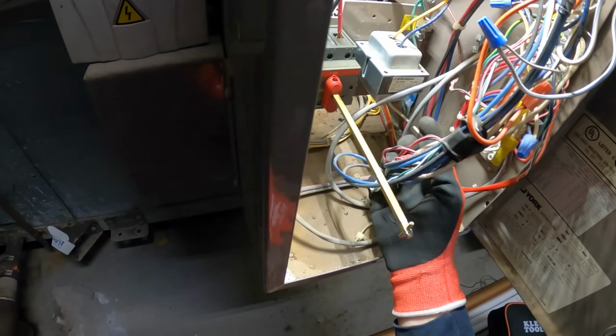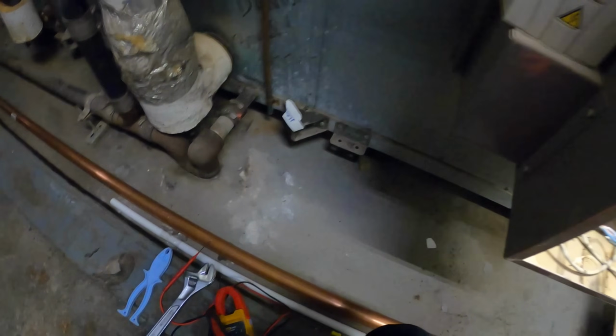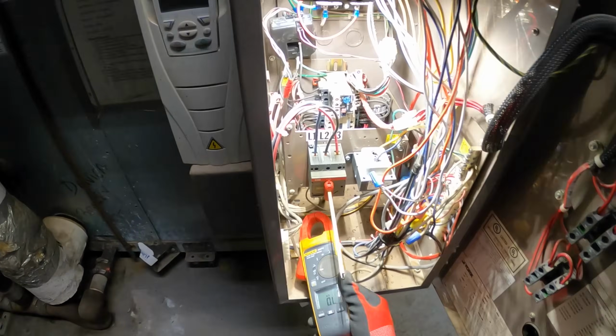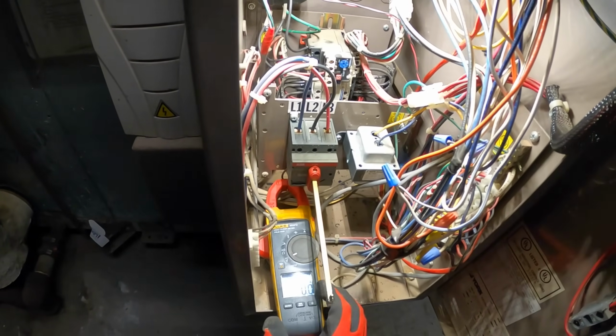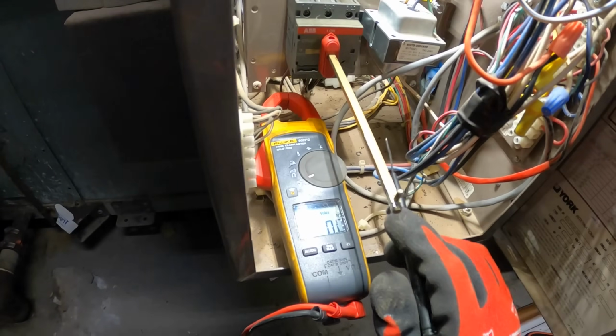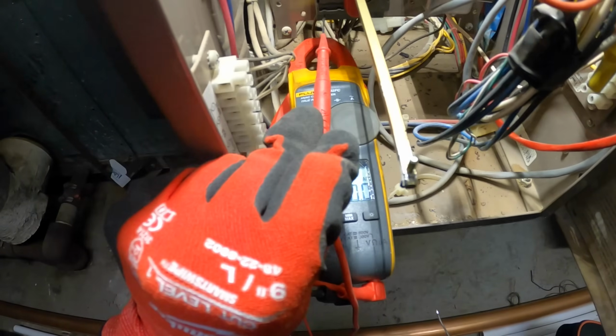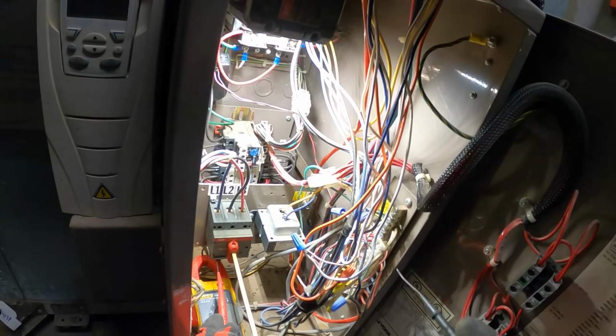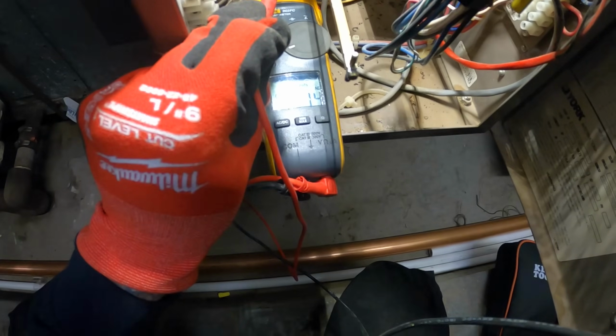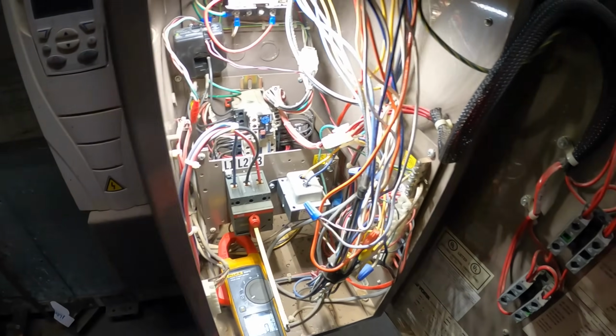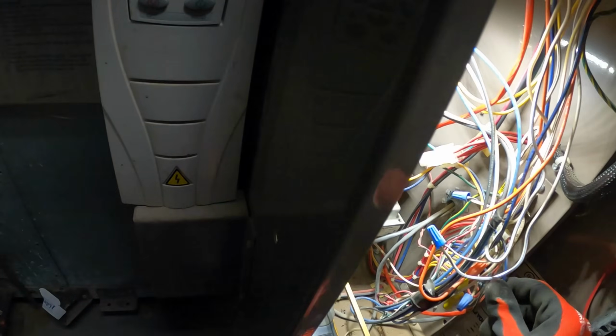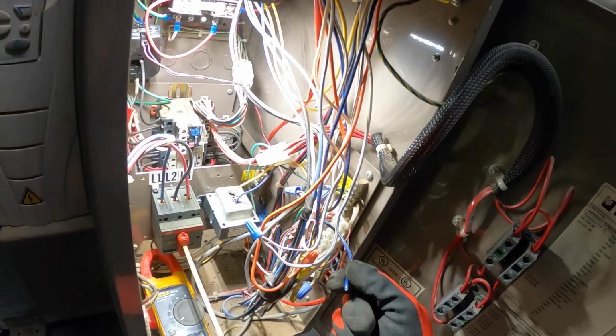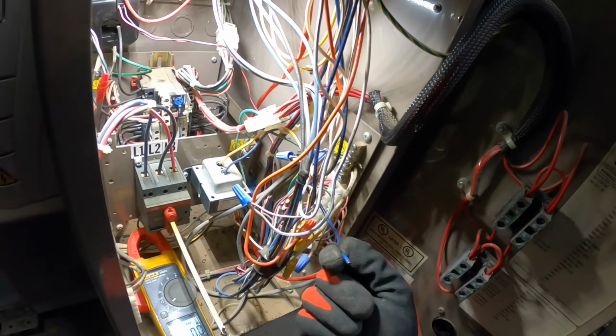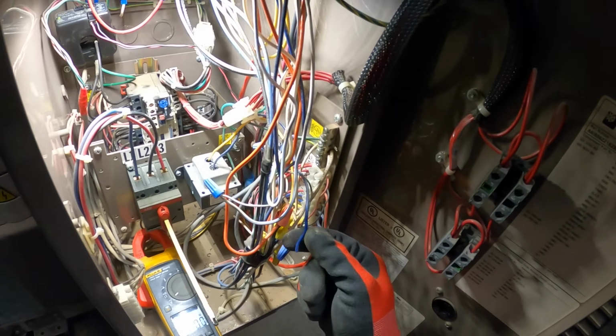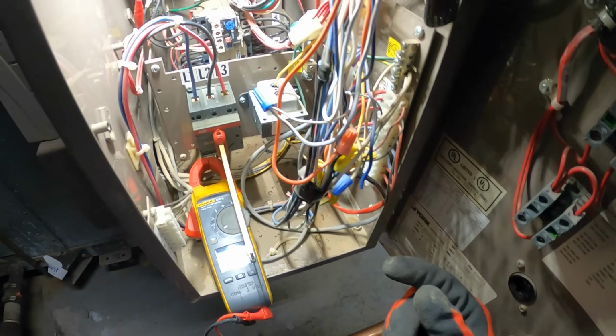What about this transformer? Got two wires on the bottom. Is the transformer getting power? This is a very simple transformer. We got one wire going in here, the other one to neutral. We got 120, I don't know if you guys can see, we got 120 going to it. Then the other wire, whoa, look. This wire right here goes nowhere. Hold on a second, that wire goes nowhere.